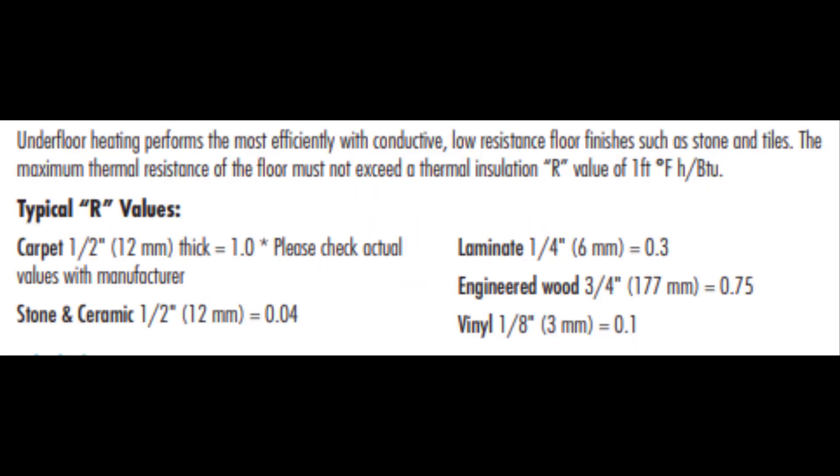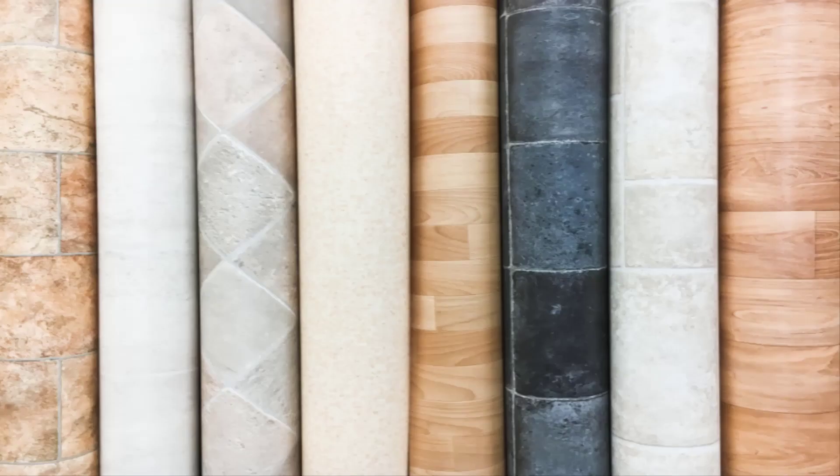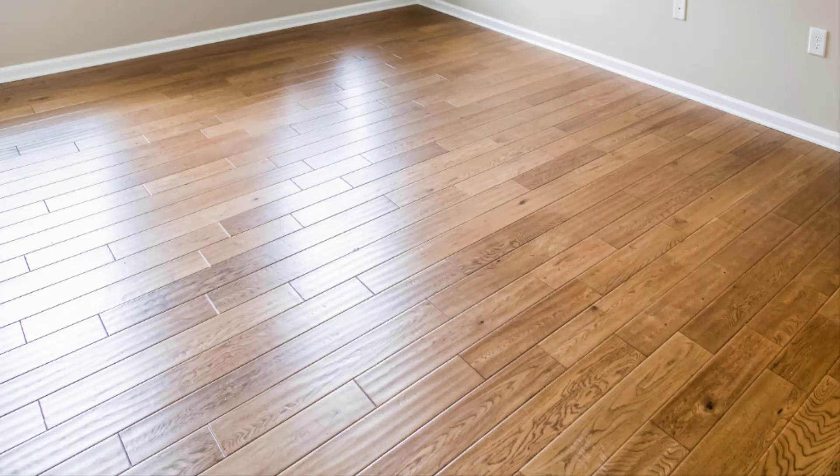As you may or may not know, strata heat can be installed under tile, stone, laminate, carpet, wood floors — you name it. But what a lot of people don't consider is that the type of finished flooring is actually going to have a large impact on whether strata heat systems can be relied on as a primary heat source. For example, tile and stone are going to be the most efficient when installing over a strata heat system, as the nature of the product allows you to run at maximum temperature if desired. With laminates and vinyl floors, you have to check with the finished flooring manufacturer to see the max temp that can be used with those products. Wood and carpet are typically the least efficient finished flooring over radiant heat systems and would not be optimal choices in poorly insulated rooms, as their density does not allow heat to transfer through the material and up into the room easily.